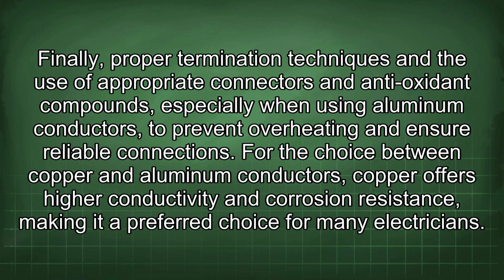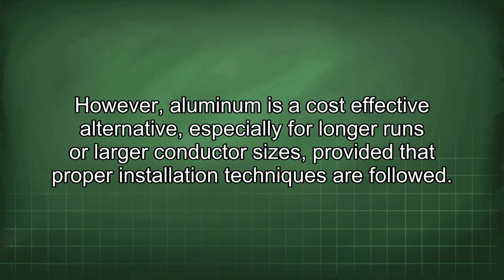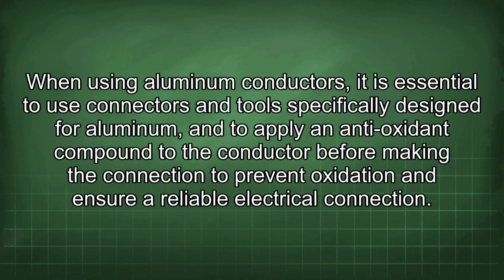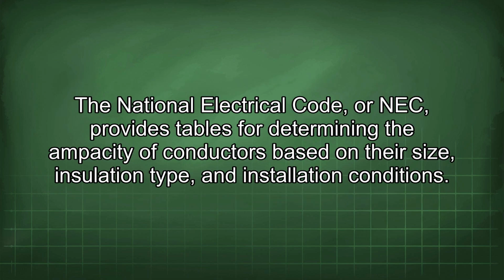For the choice between copper and aluminum conductors, copper offers higher conductivity and corrosion resistance, making it the preferred choice for many electricians. However, aluminum is a cost-effective alternative, especially for longer runs or larger conductor sizes, provided that proper installation techniques are followed. When using aluminum conductors, it is essential to use connectors and tools specifically designed for aluminum, and to apply an antioxidant compound to the conductor before making the connection to prevent oxidation and ensure a reliable electrical connection. The National Electrical Code, or NEC, provides tables for determining the ampacity of conductors based on their size, insulation type, and installation conditions.